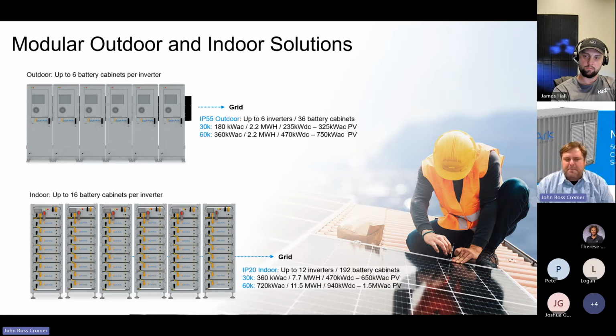If it's for backup power and you want that pass-through capability, one inverter will work. But given these are commercial projects and the inverters only cost about 15 grand, I think it's a good idea to start with whole building backup, not just backing up one 200 amp load center off the building. If you're trying to do whole building backup and add some redundancy, starting with 2 inverters and 2 battery cabinets as the minimum project size is a good idea.